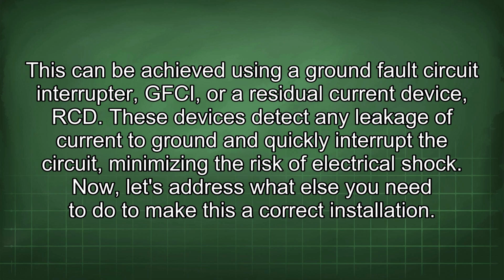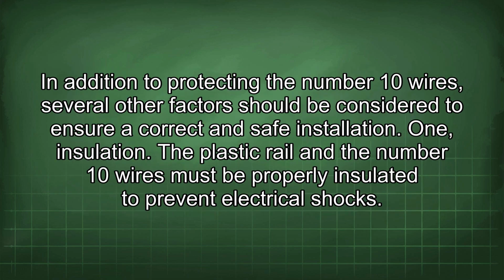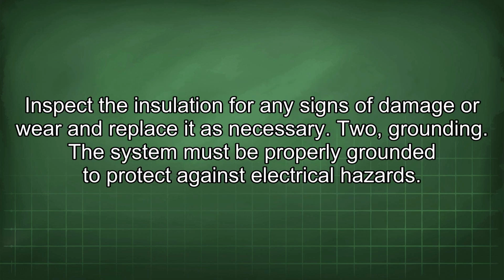This can be achieved using a ground fault circuit interrupter, GFCI, or a residual current device, RCD. These devices detect any leakage of current to ground and quickly interrupt the circuit, minimizing the risk of electrical shock. Now, let's address what else you need to do to make this a correct installation. In addition to protecting the number 10 wires, several other factors should be considered to ensure a correct and safe installation. 1. Insulation. The plastic rail and the number 10 wires must be properly insulated to prevent electrical shocks. Inspect the insulation for any signs of damage or wear and replace it as necessary.